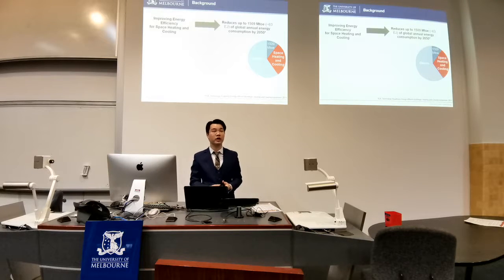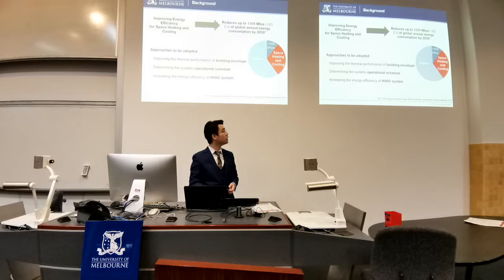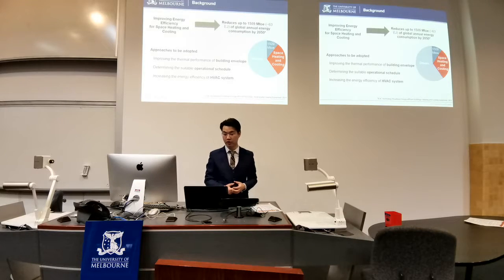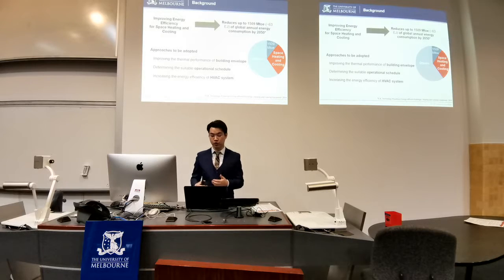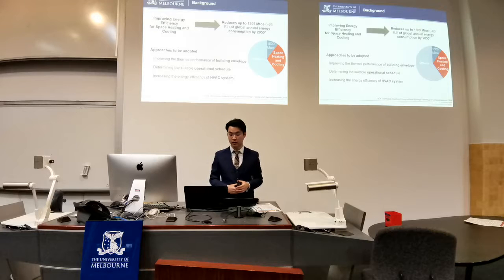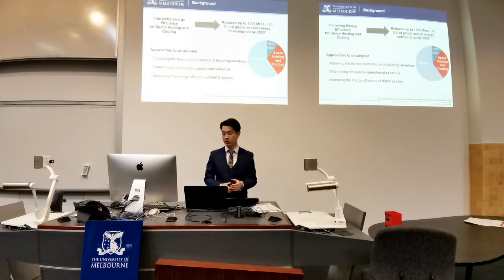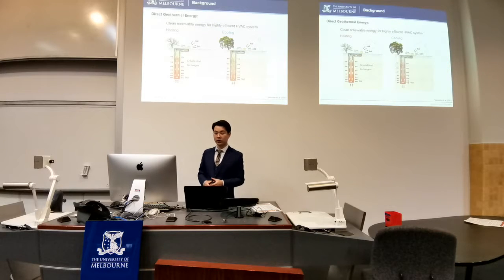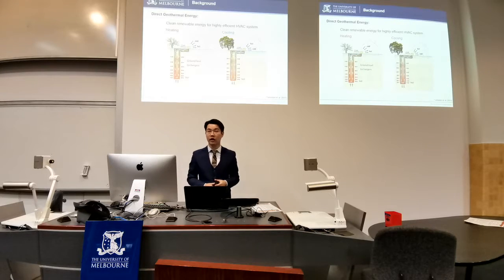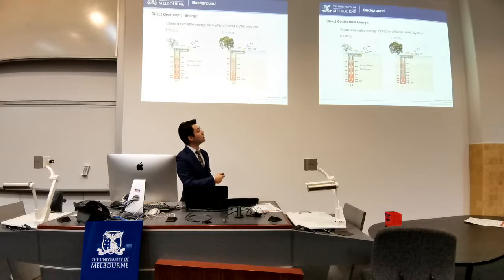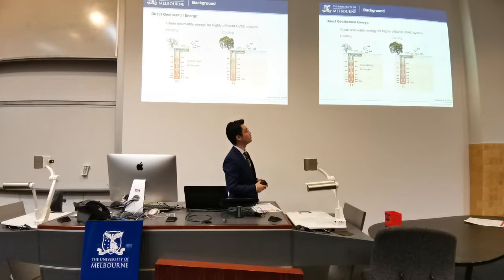There are several approaches we can adopt to achieve this goal, including improving the thermal performance of the building envelope, determining a suitable operational schedule, as well as increasing the energy efficiency of heating, ventilation, and air conditioning systems. Direct geothermal energy can be used as a clean and renewable source for highly efficient HVAC systems. When heating, heat is extracted from the ground into the building via ground source heat pumps and ground heat exchangers. When cooling, the reverse cycle happens, meaning heat is injected into the ground via the ground heat exchangers and the ground source heat pumps.